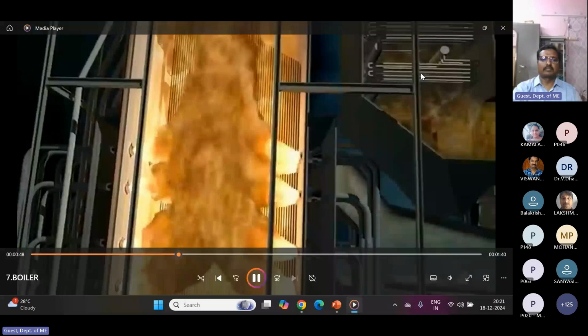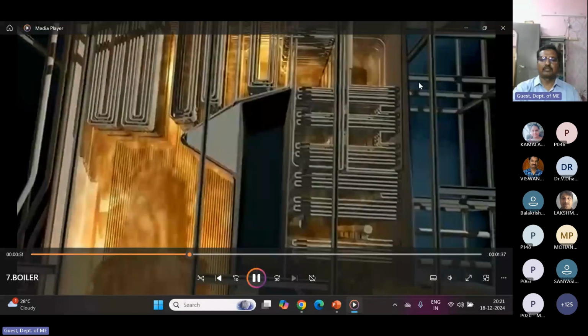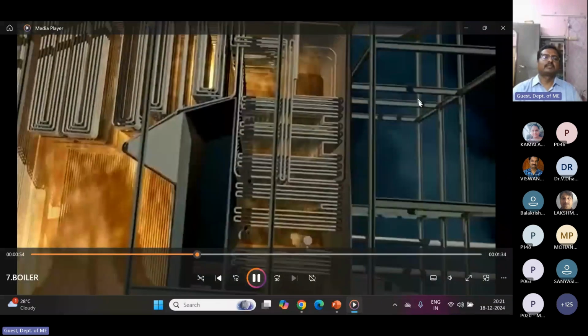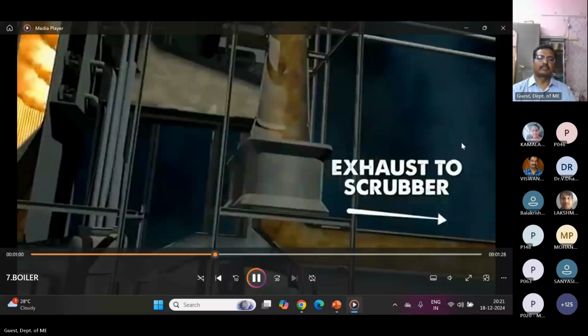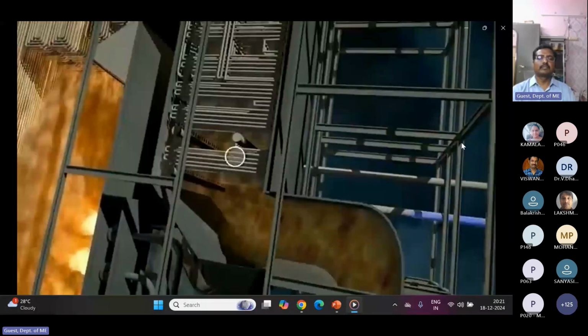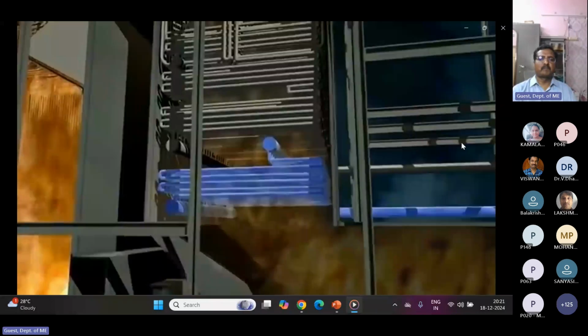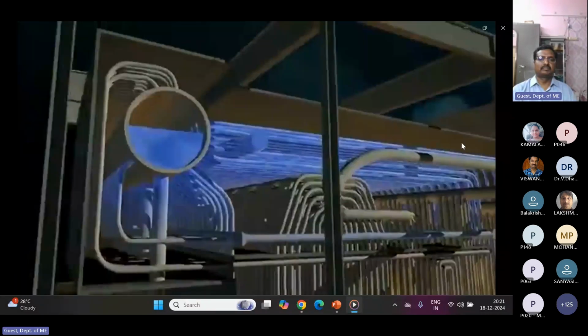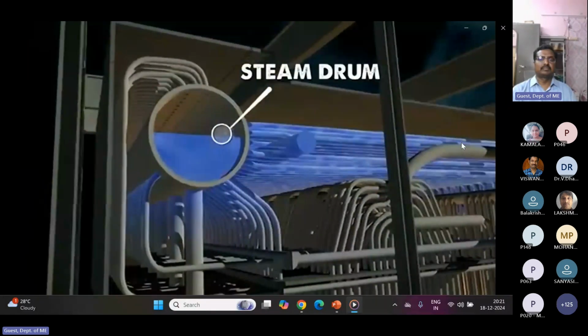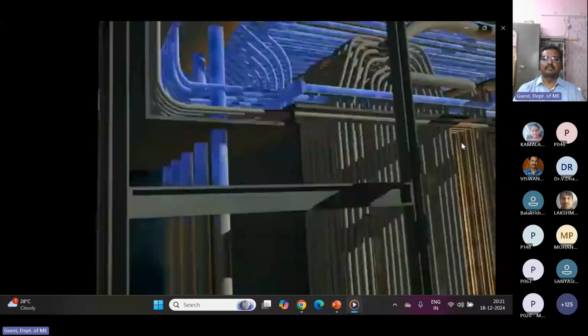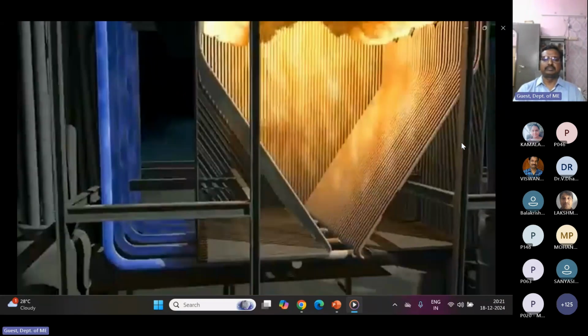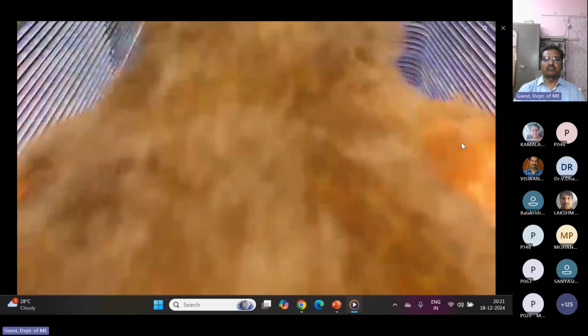The hot gases flow upward, heating the rest of the system through convection, before passing through the air preheater and ultimately flowing into the scrubber, where pollutants are removed. Liquid water is pumped into the system at the economizer. Gradually, it's heated to saturation temperature before gathering at the steam drum, the system's main distribution hub for circulating water and steam through the boiler. Liquid water flows through large downcomers and into the base of the firebox. A network of 2-inch tubes lines the firebox walls, and burners force feed a continuous supply of combustible fuel into the ultra-hot firebox. Eventually, the insides of the firebox burn so hot that its surrounding steel walls would melt if not for the tube-lined walls of liquid water.